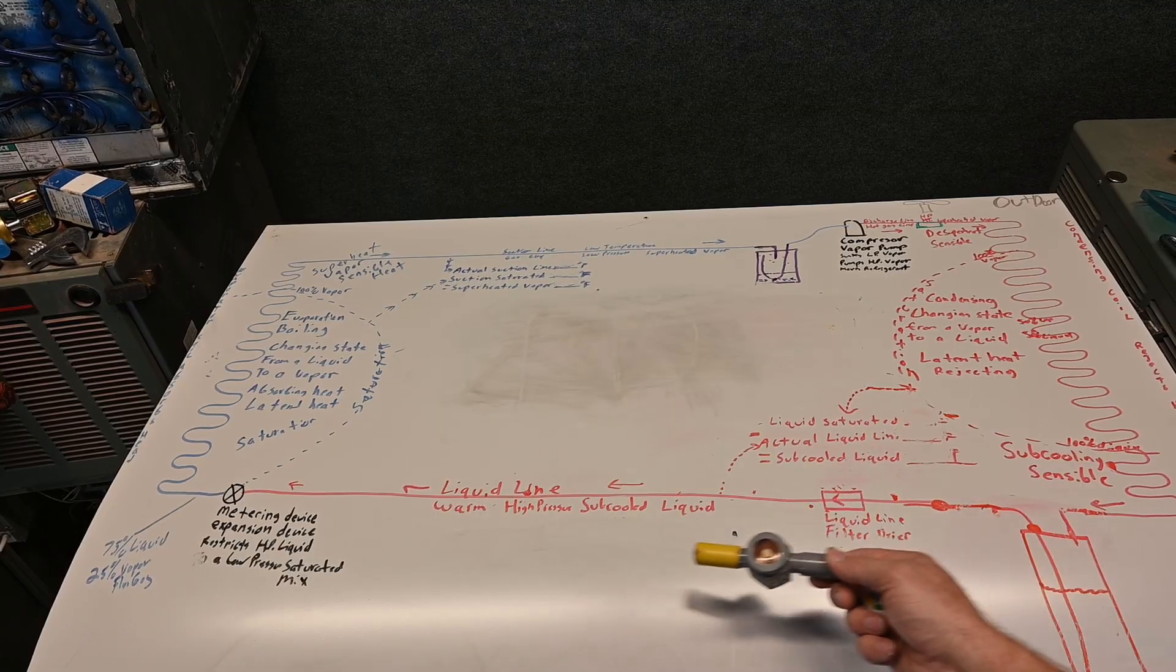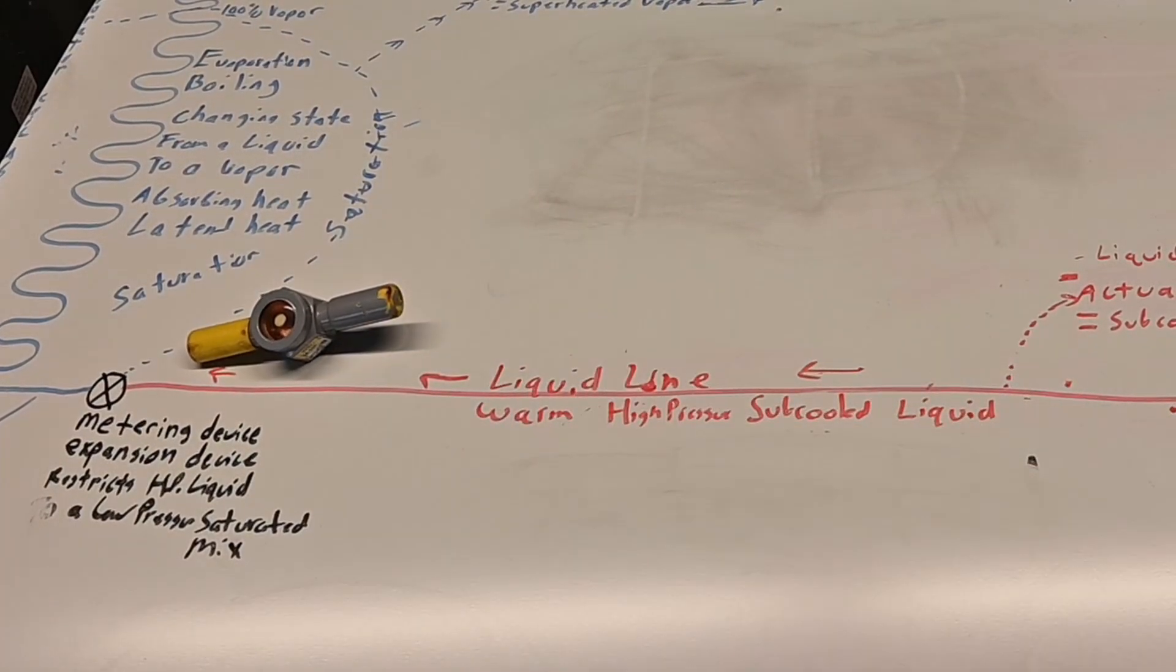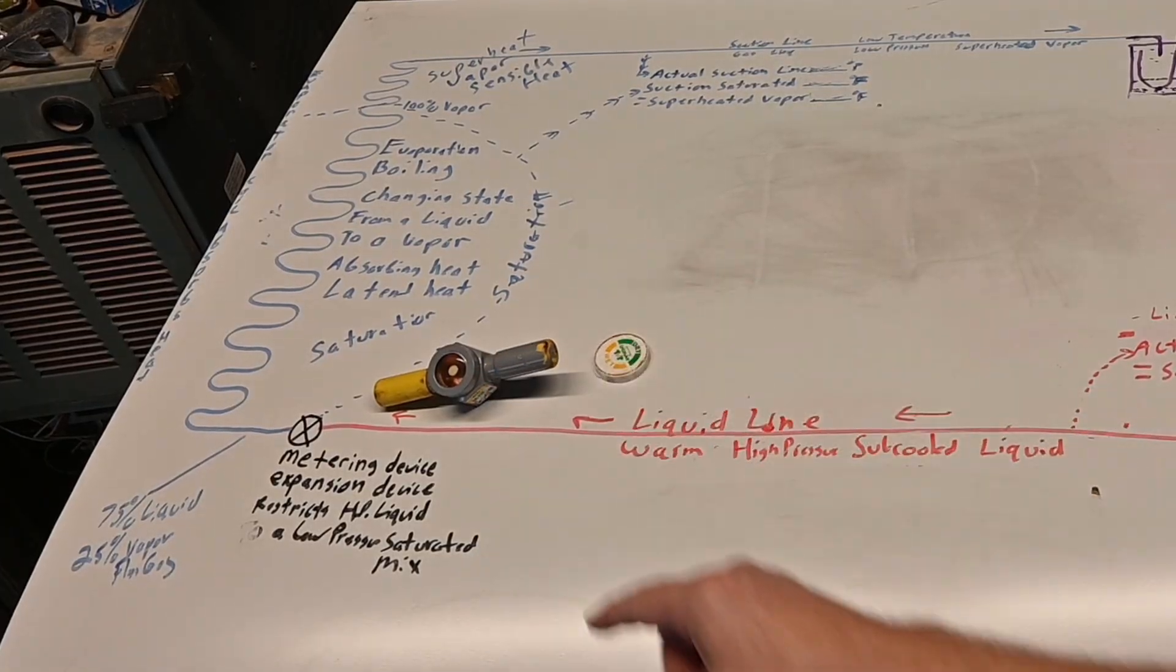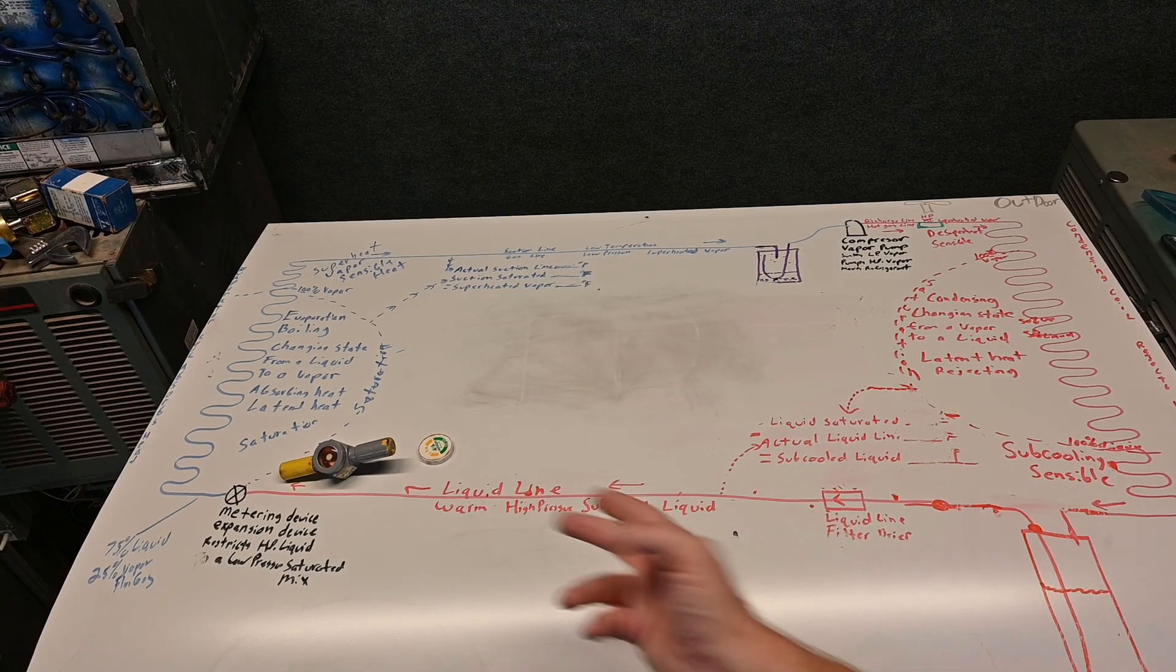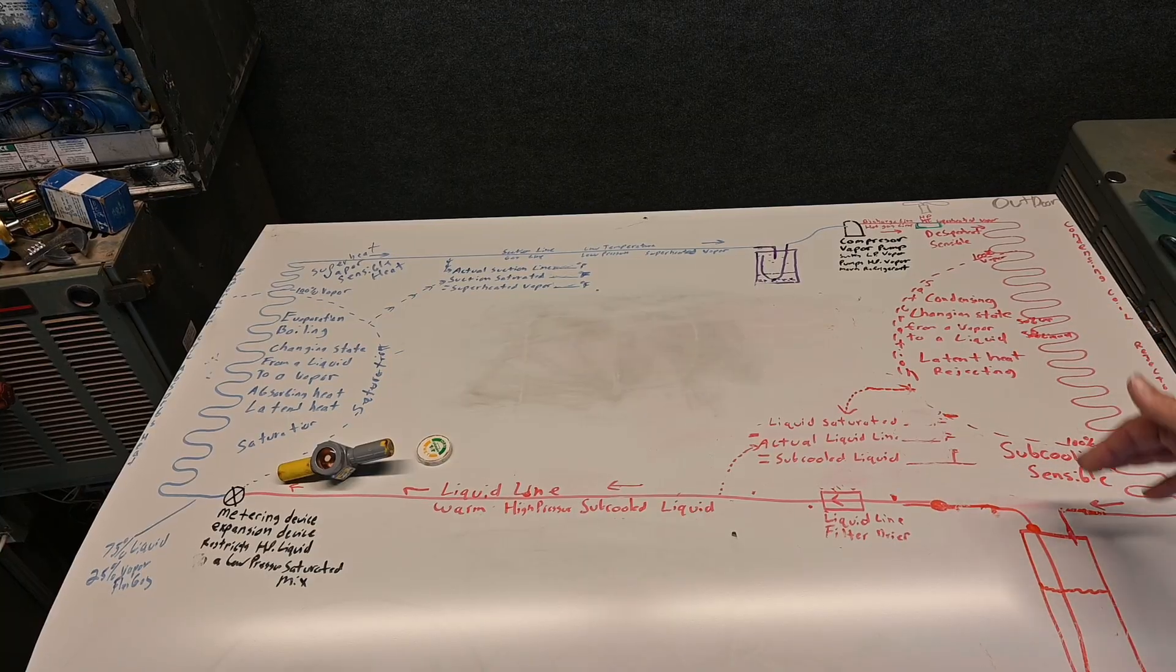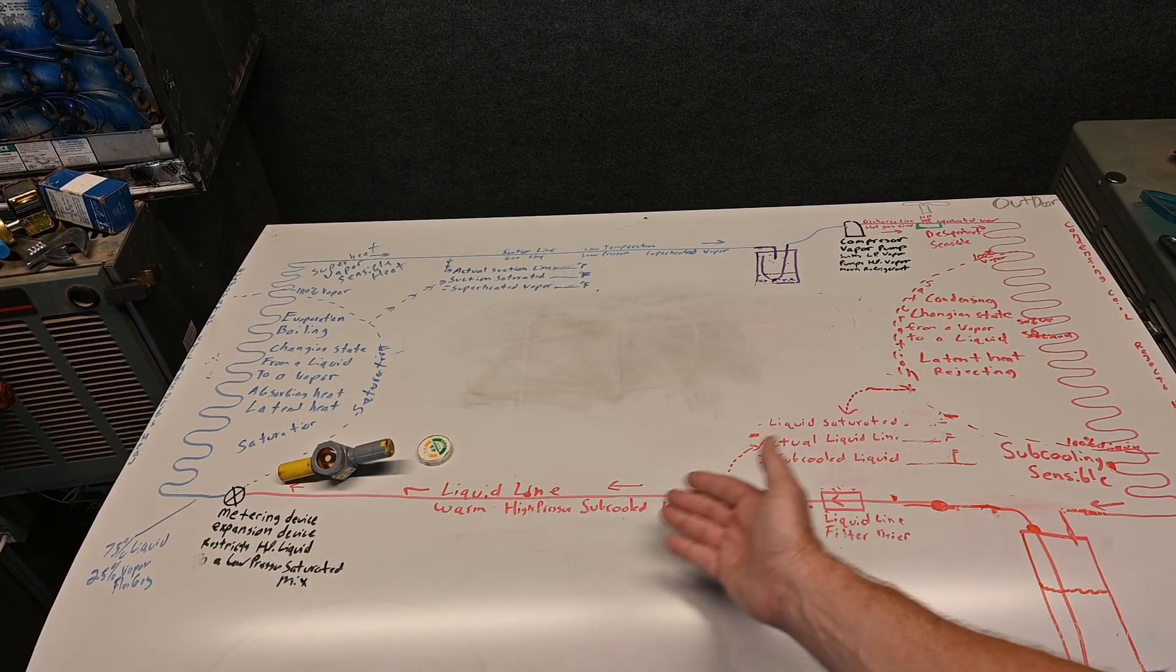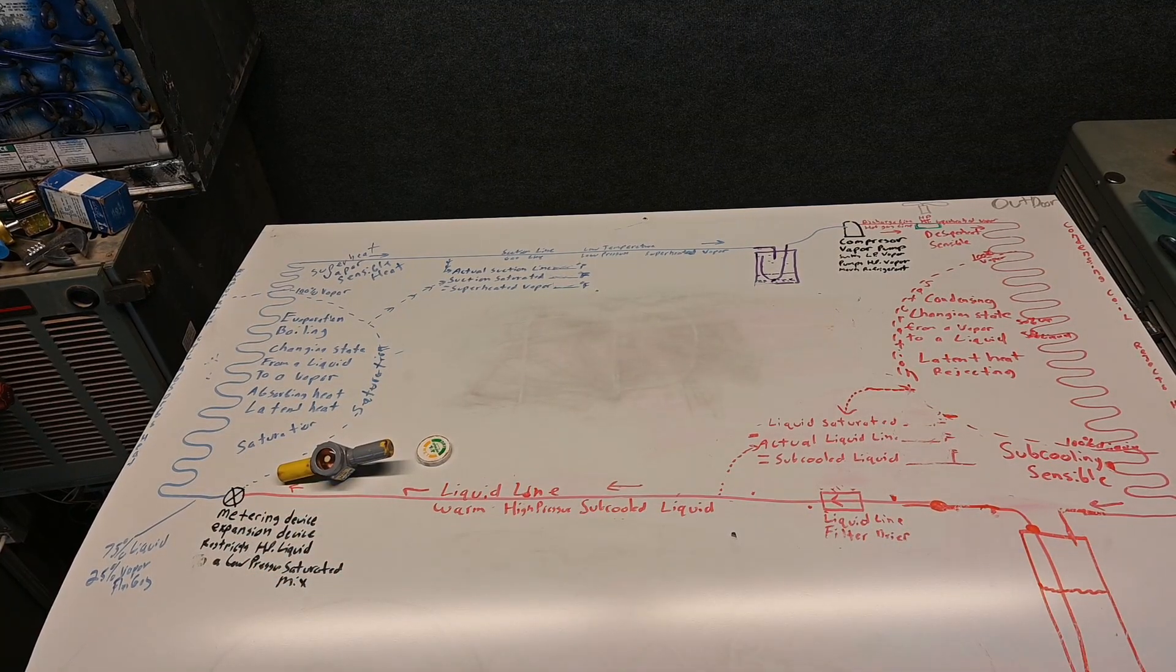Now if I do install these in residential, I like to put it right before my metering device. The reason I like it there is because I can tell not only if I have moisture, but also that I have enough subcooled liquid coming over here to my metering device. Remember, the metering device meters liquid refrigerant. So even if I have enough subcooling over here, maybe I have a restriction somewhere, maybe the attic's too hot and I'm losing my subcooling, and I can see if I have liquid refrigerant before I get to my metering device.